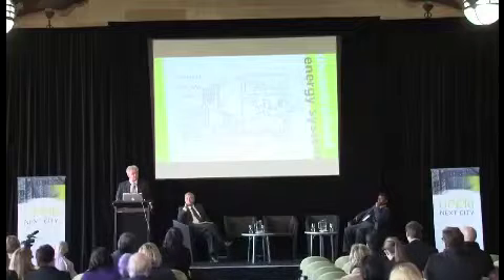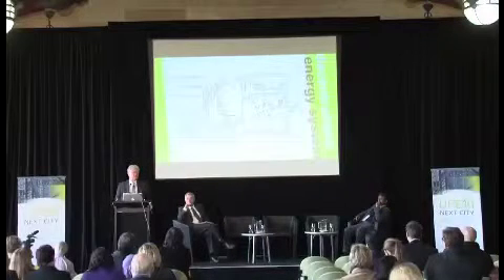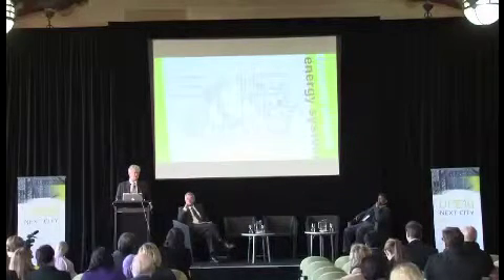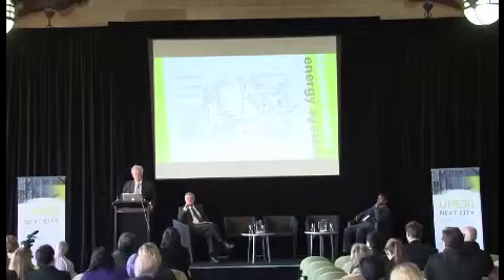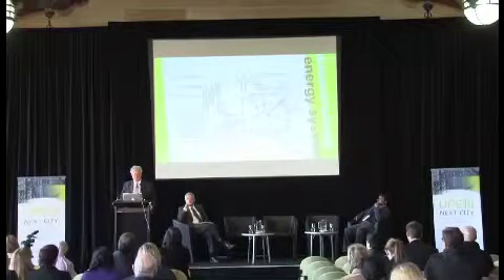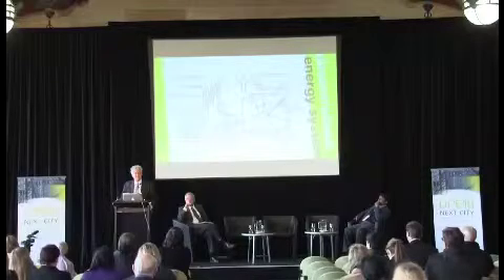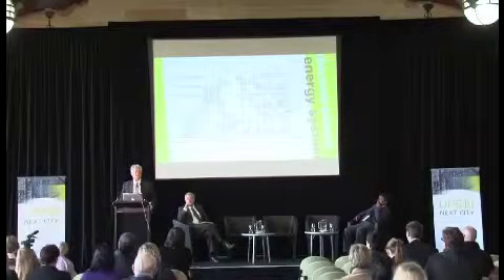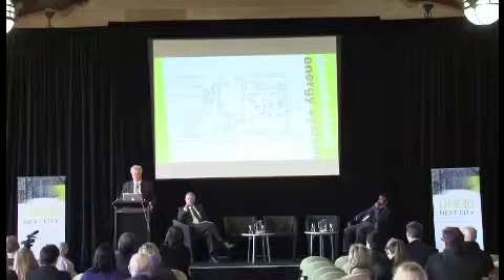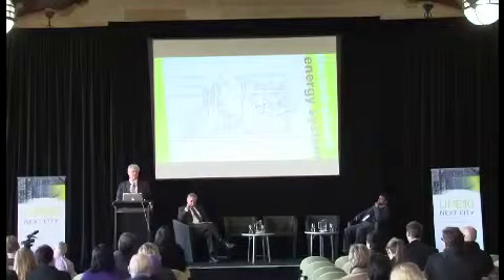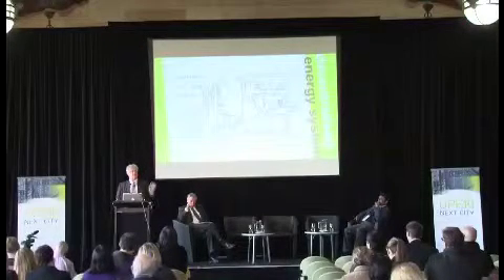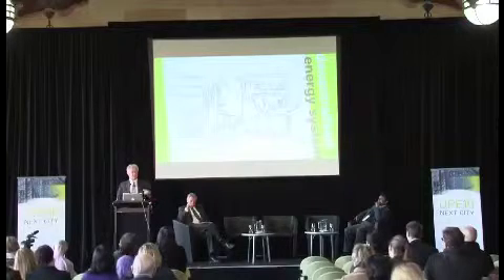A typical boiler-in-a-basement scheme will probably deliver something like a 15% energy hit for that particular building. Precinct systems of the type I installed in Woking in London were typically 125 to 135% — the buildings were self-sufficient, with between 25 and 35% available as export, not exported to the grid, but within the city.